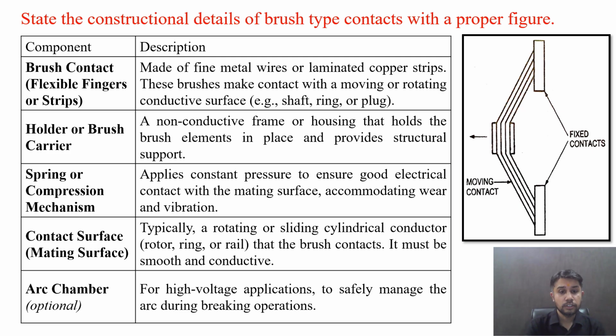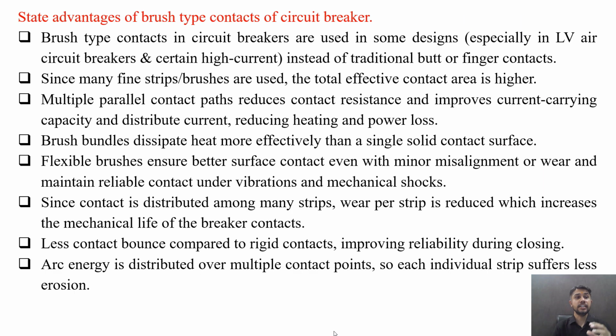Arc chamber. For high voltage applications, to safely manage the arc during breaking operations, an arc chamber is placed, and it is optional. So in this, these are the fixed contacts of the brush and these are the moving contacts moving outside. This is the rotating contact in between. So this is how brush type contacts are used in the circuit breaker.